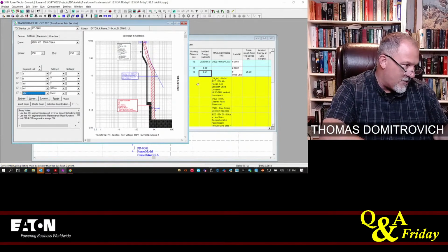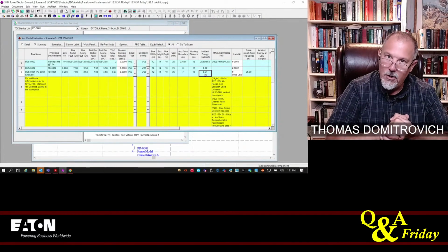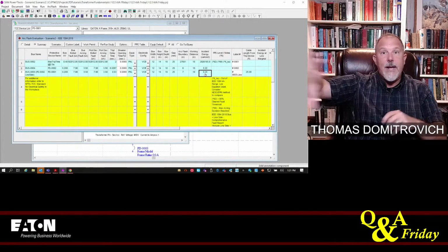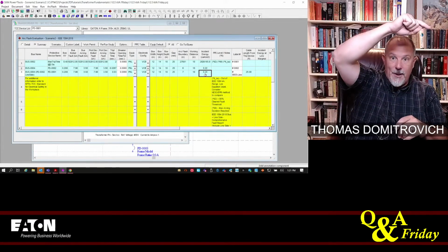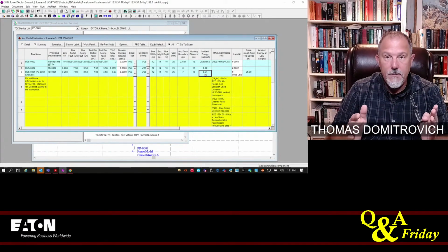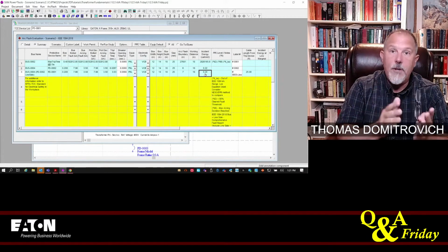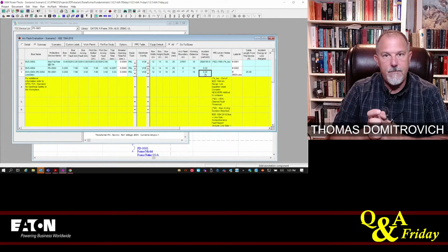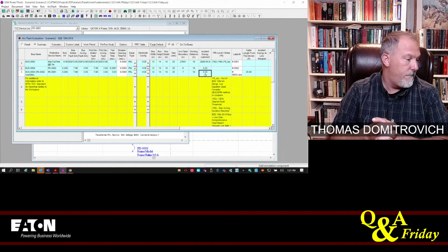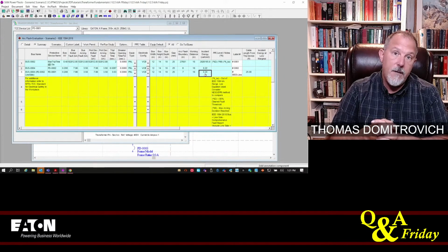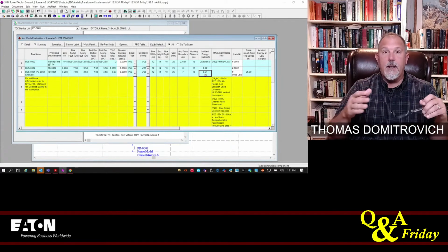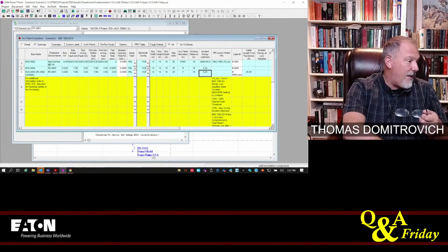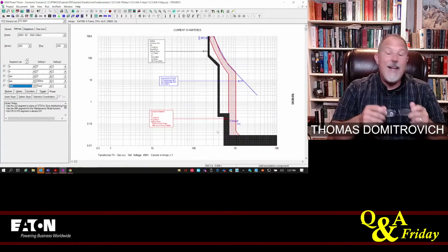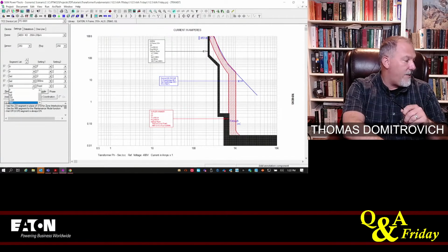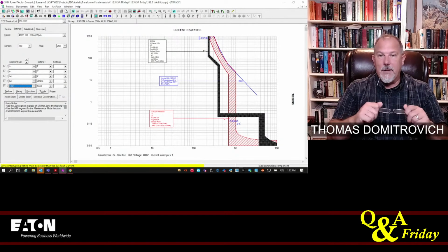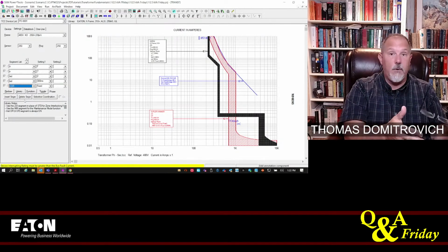And look at my incident energy, 0.24. So I didn't break out the secondary. I turned maintenance mode on the primary of the transformer on that feeder breaker. And now I have 0.24 calories on the secondary, just because I turned maintenance mode on. But now, Wiley, you have to buy an electronic trip unit for the primary to get a trip curve that has that type of flexibility. When I turn maintenance mode back off again and I go back to instantaneous, now my delay is back in the picture. That is exactly what maintenance mode does for you.